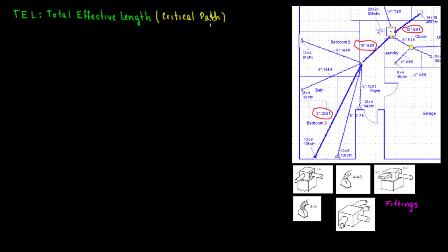You might be wondering: what is the critical path? The critical path is actually the longest path based from the return to the farthest supply. So we have the farthest return right here and the farthest supply right here — the supply register. That complete length is going to be the TEL, the critical path.